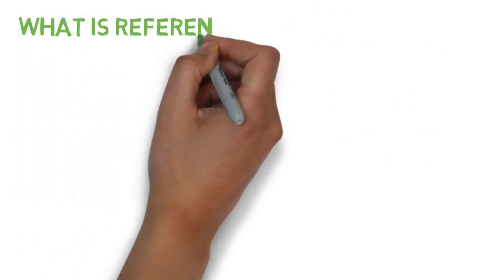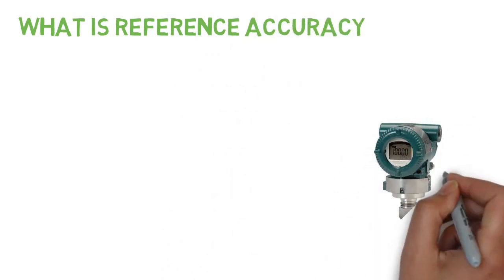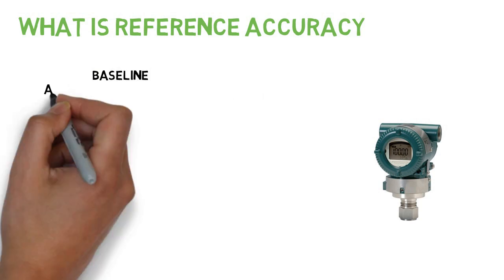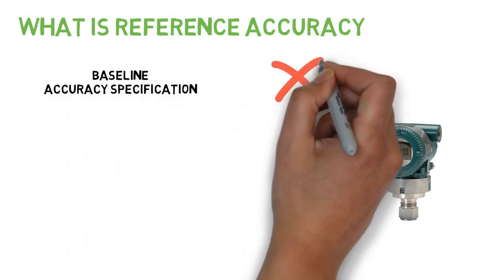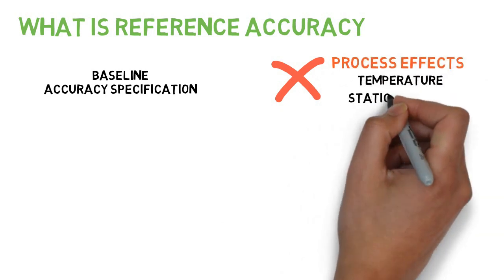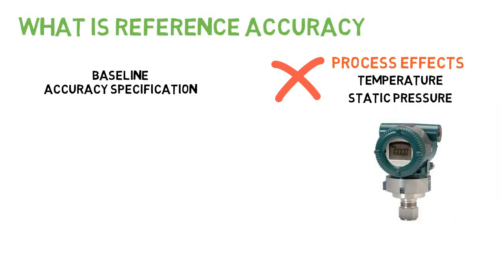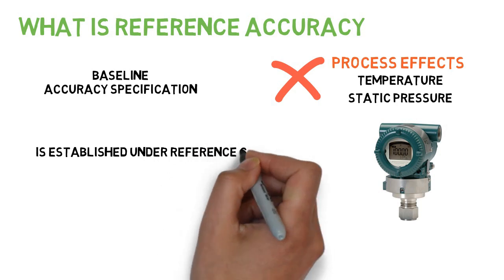What is reference accuracy? Reference accuracy is a baseline accuracy specification that does not include process effects such as temperature and static pressure effects. Reference accuracy is established under reference conditions.